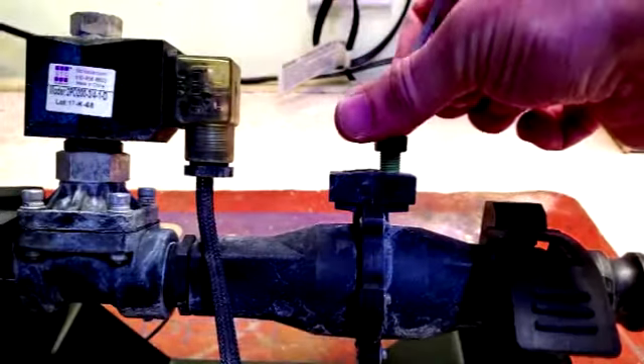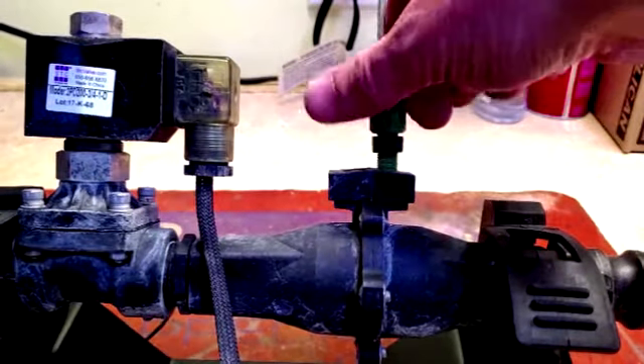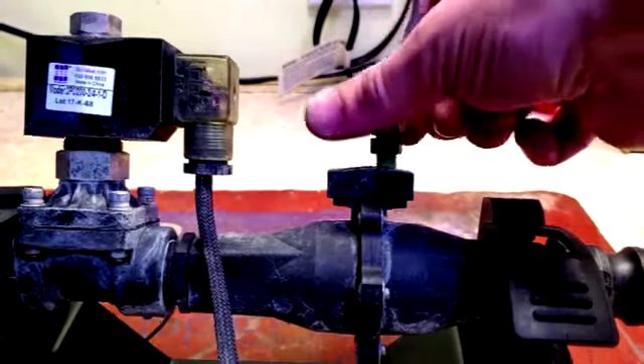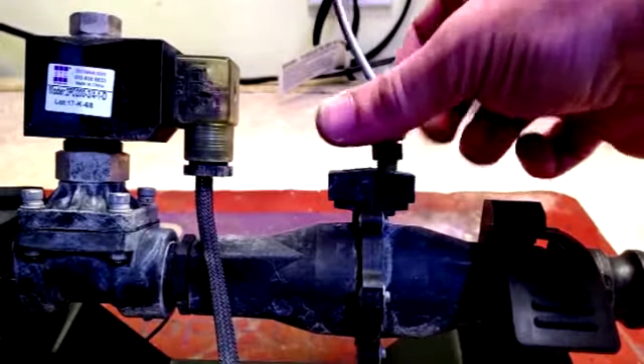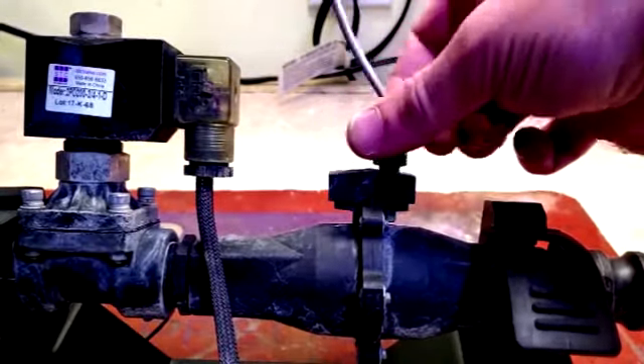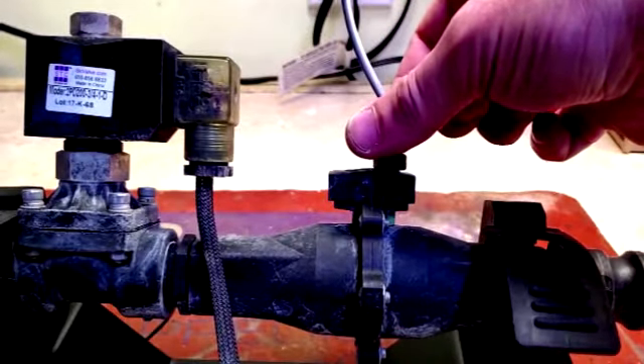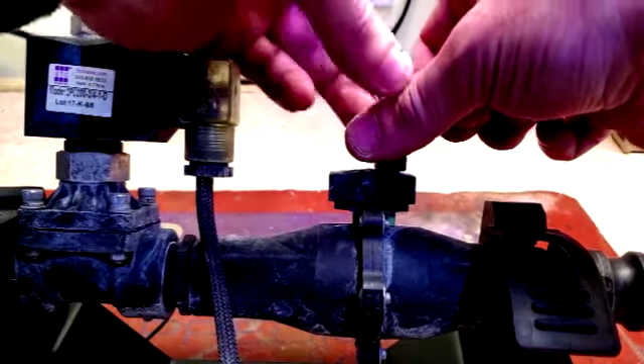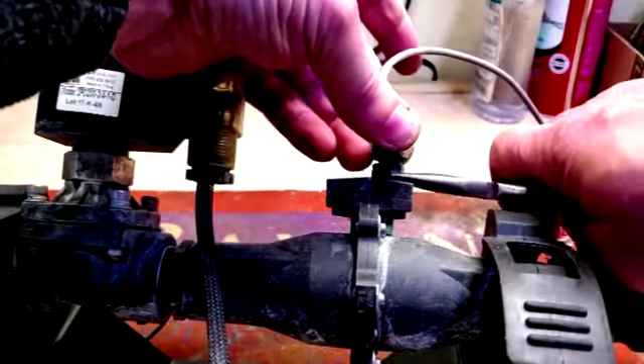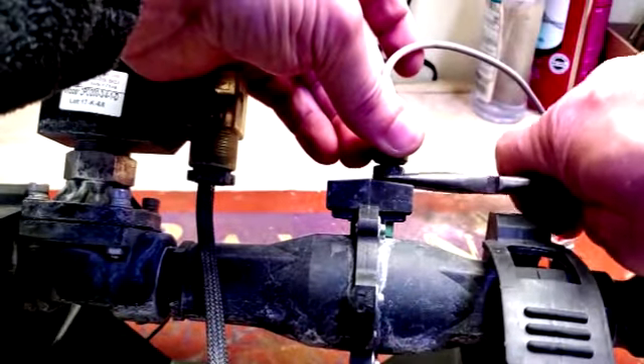So let's replace the sensor now. We're going to very carefully re-screw this into that little brass nut or stainless nut that's inside of there, and do it from the sensor side. Be mindful of the wire. We're going to walk that all the way down until it just hits the base of the flow meter housing, and I'm going to give it just a little tweak past that.